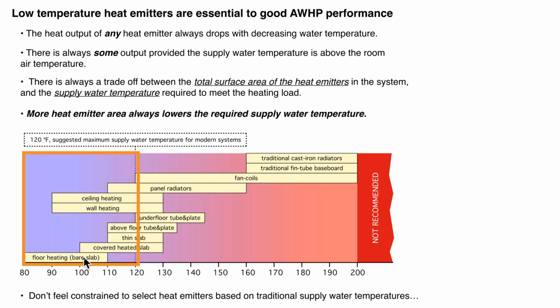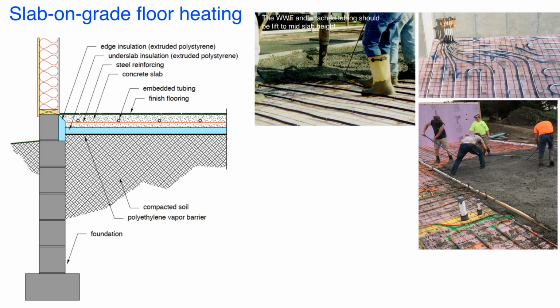Now, when we put a floor covering of some sort, it could be a thin engineered wood plank, it could be ceramic tile, you can see we are forcing that water temperature up. How high does it go? It depends on the R value of that covering. So we're always looking to minimize the R value of any floor covering we're putting on there. There are some systems that use aluminum plates above the floor and below the floor. They are going to require some higher temperatures. It is possible to keep them in that 120 range. The way you're going to do that is with close tube spacing, plenty of aluminum plates, and minimal resistance in the floor covering. And then I'm going to show you a couple examples today of ceiling and wall heating as well. All right, so let's start with the slab on grade.